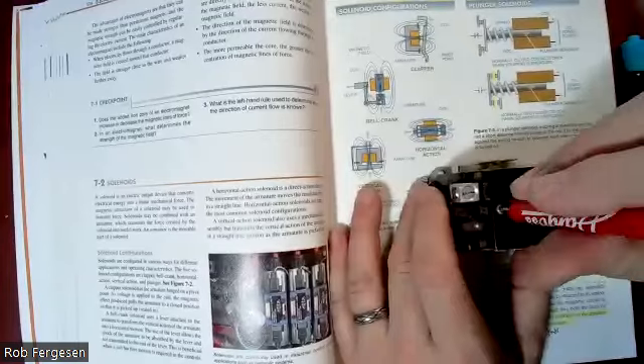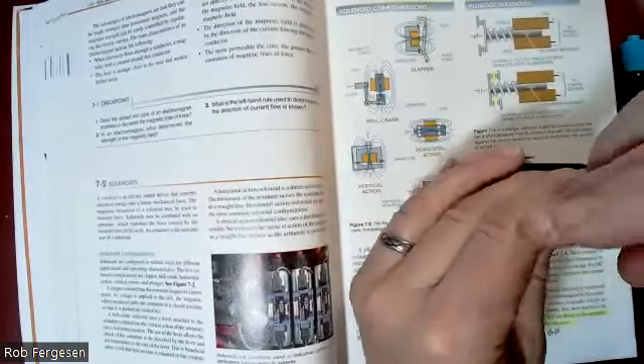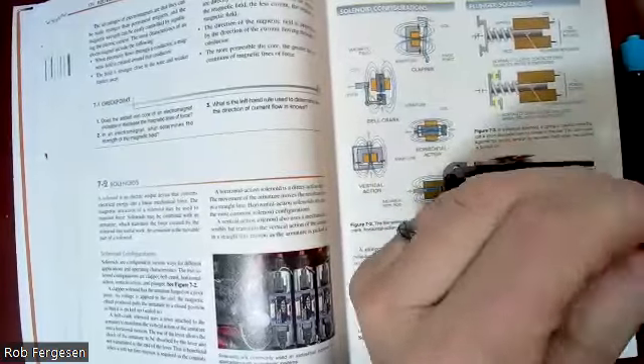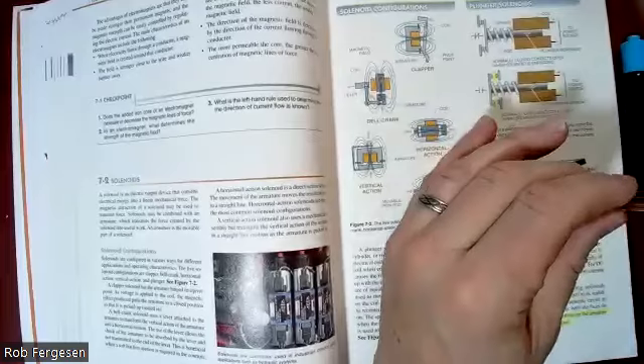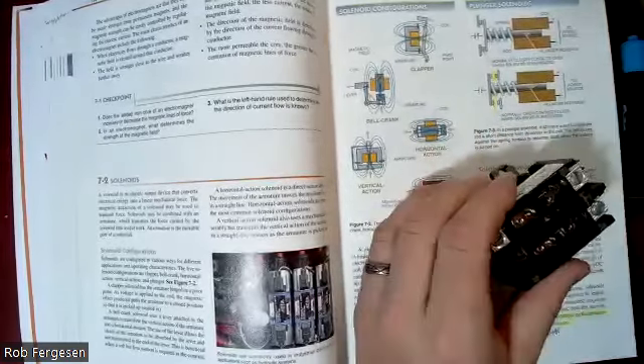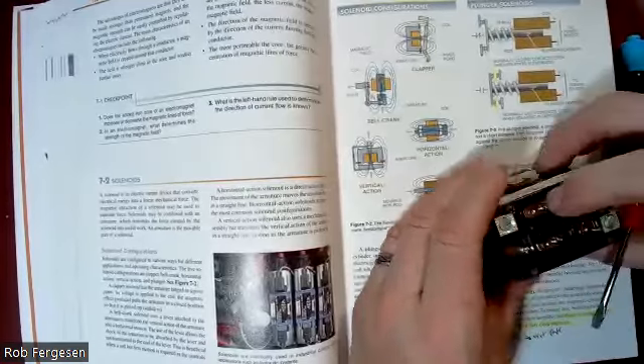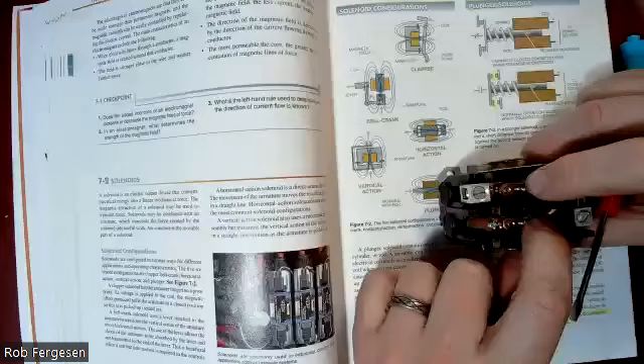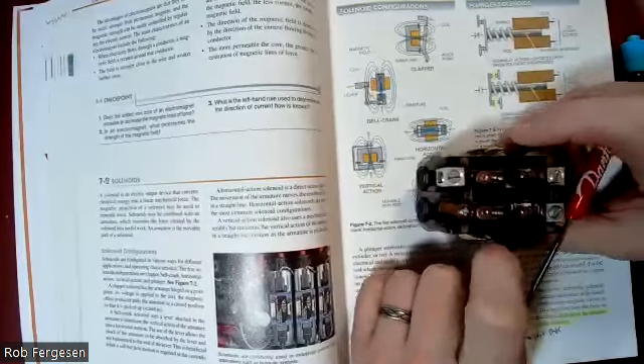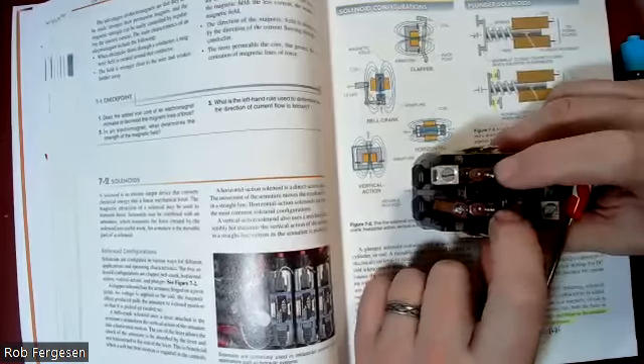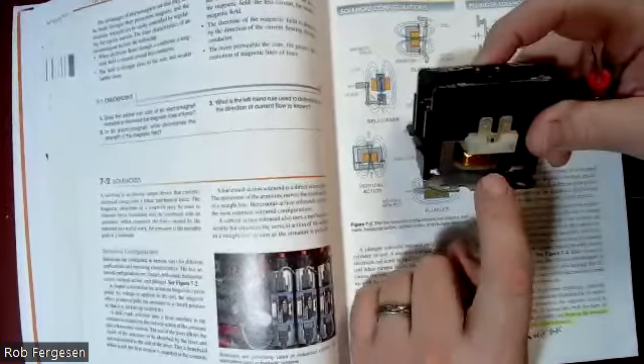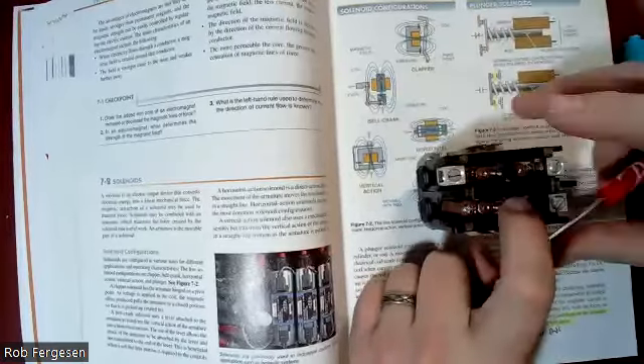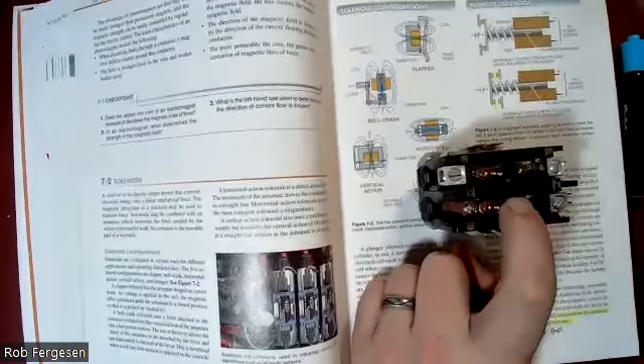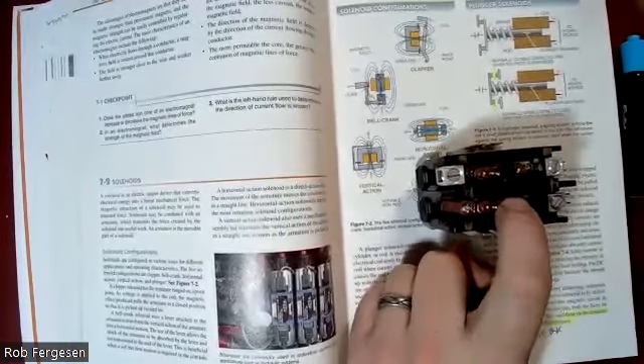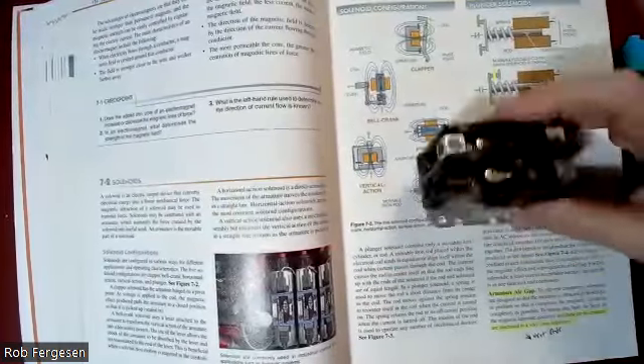Remember, we popped this open, we found the contacts inside there, and it sucks down the metal frame that's spring-loaded and mounted with contacts. So it basically sucks one magnetic plate down against another magnetic plate. If I press this down, this whole thing is spring loaded, and it's attached to a little steel plate that gets sucked down. All I'm doing here is creating a little magnet that sucks down this plate against the force of that spring. So the spring separates them, and then the magnetic force sucks it down. And that creates my solenoid. And that's one configuration, right?